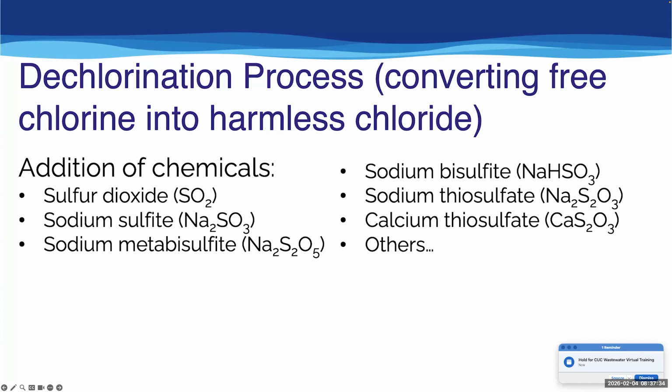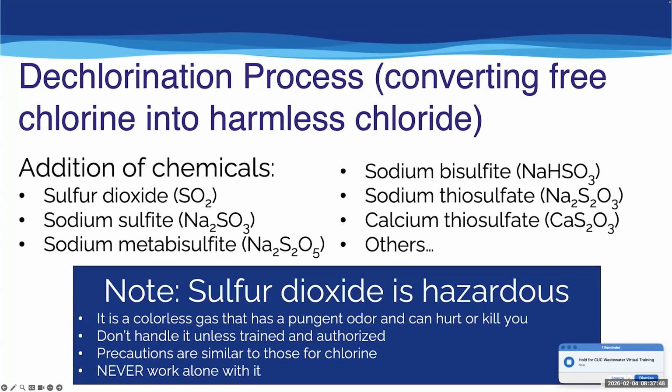The process, particularly when you're using sulfur dioxide, is really, really fast and really, really efficient. So it's, again, one of the most common dechlorination agents being used. That being said, sulfur dioxide is hazardous. We'll go into this a little bit more in the safety part, but I do want to point out it's a colorless gas. It has a pungent odor, and given enough of it, it can hurt or kill you.